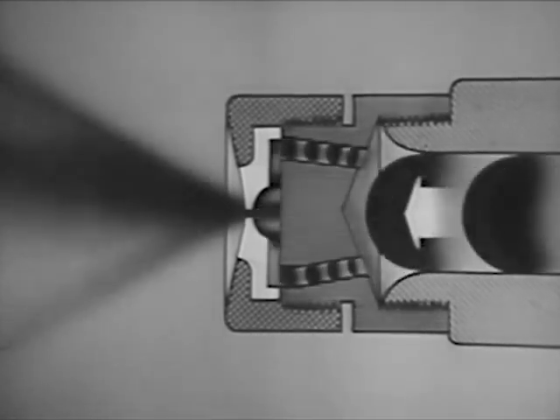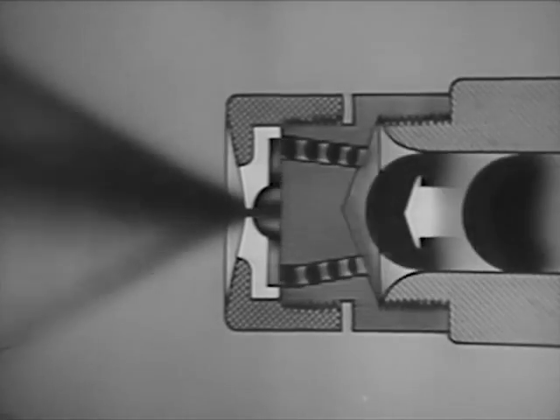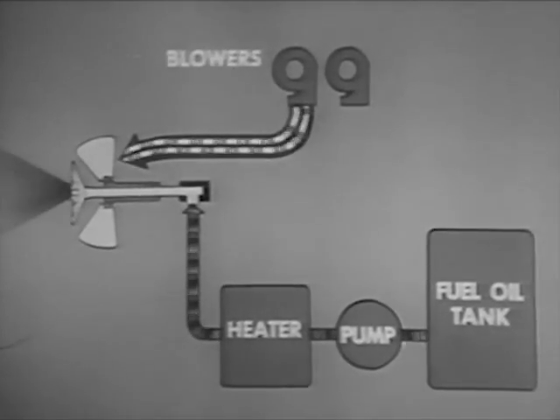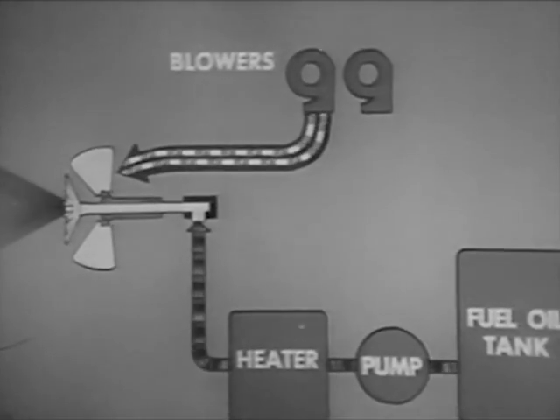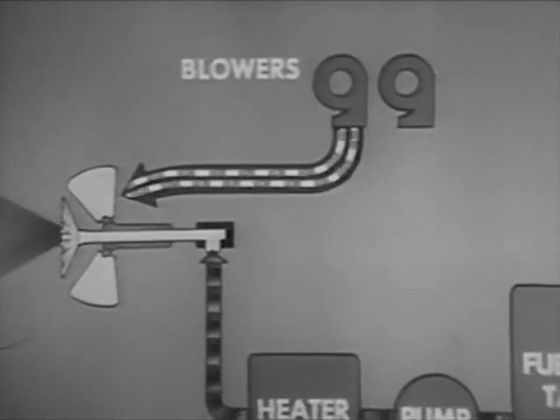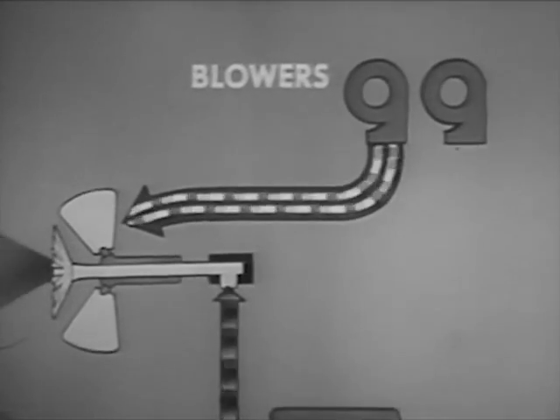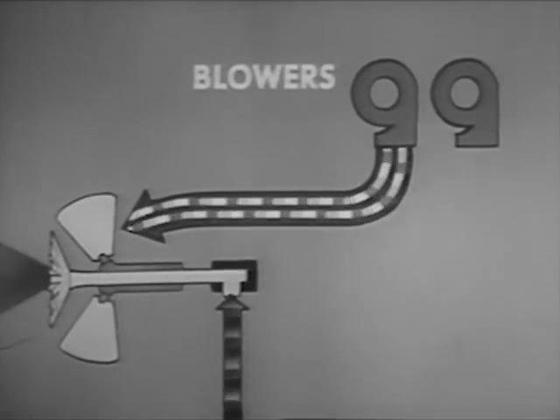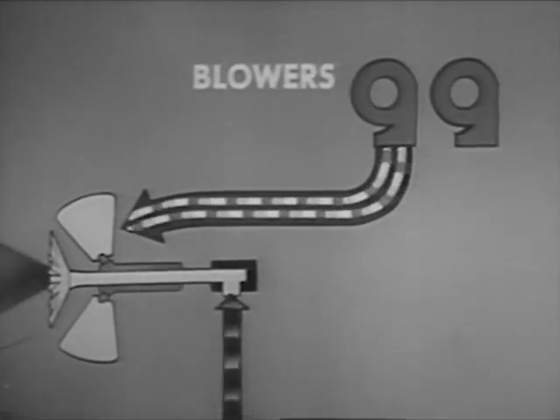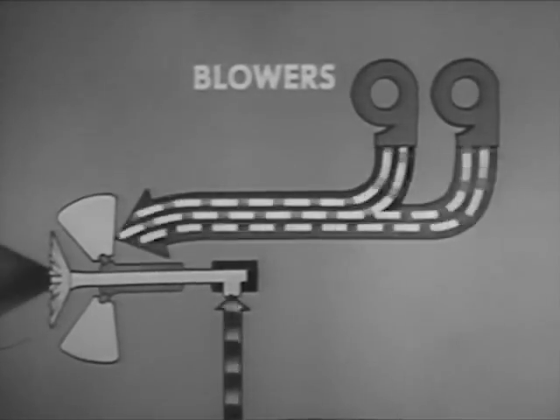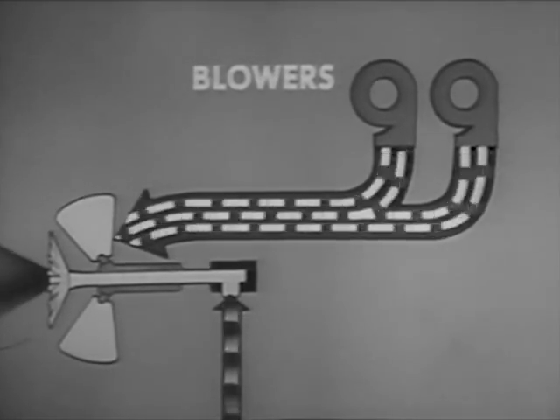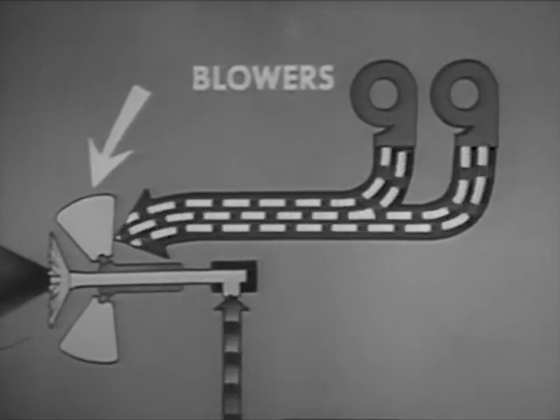Frequent changes are necessary because the operating range of a given sprayer plate is very limited. Controlling the force draft blowers is the principal method of controlling the quantity of air reaching the burner. For example, to increase the air a moderate amount, you increase the speed of the blower in service. Or, if even more air is needed, you cut in another blower. You can make minor adjustments in the air supply with the air doors.